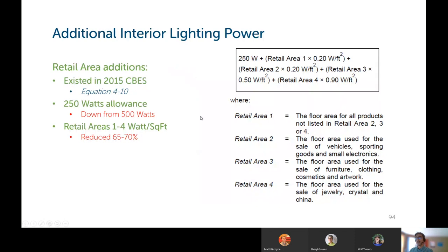Additional interior lighting power: there are additions for retail areas. This has been in the old code and the new code. There's existing wattage that's allowed for sales areas. It's equation 4-10, which I have listed up on the right in that box. The base wattage of 250 watts here that is allowed has been reduced from 500 in the previous code. And all the different retail areas, which are listed here, have an associated watts per square foot that you can add more wattage to based on the size of that retail area. And those watts per square foot have been reduced between 65 and 70% compared to the old code. So a pretty big reduction there that is likely assuming all LED installations compared to the old code.